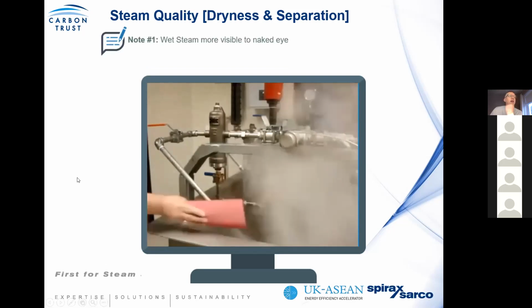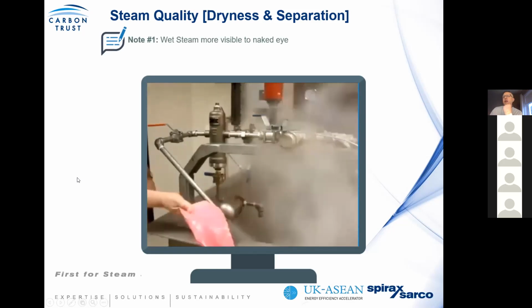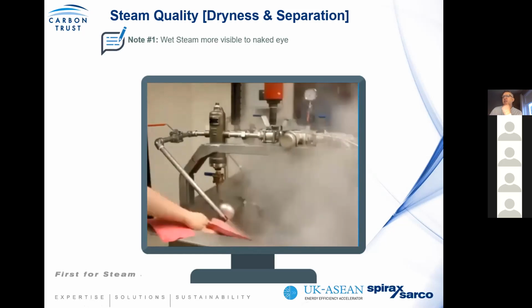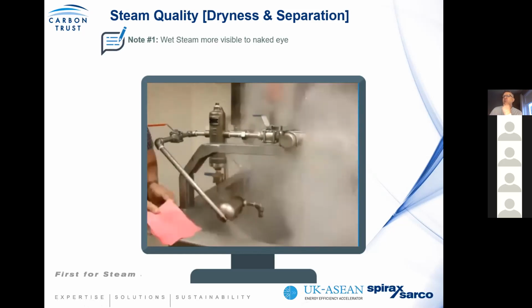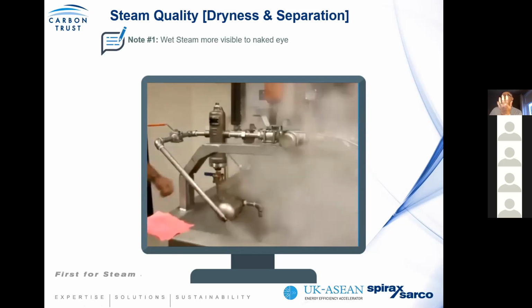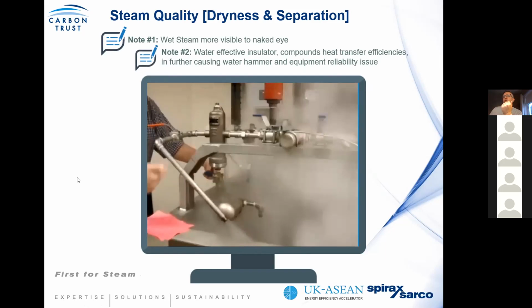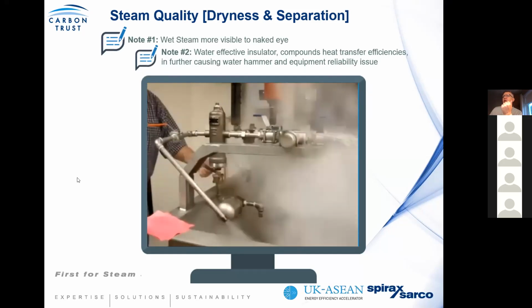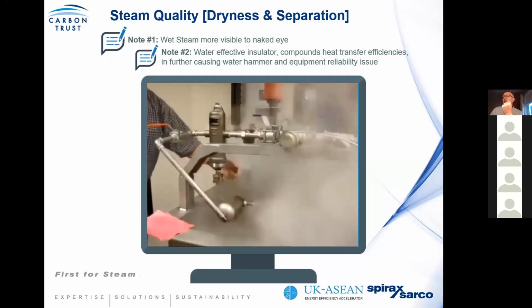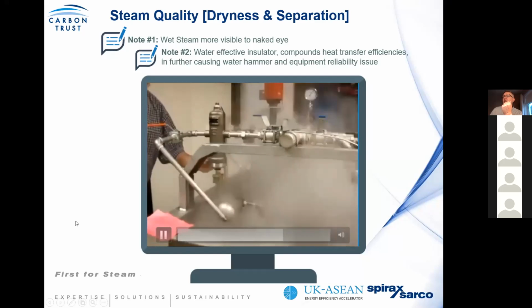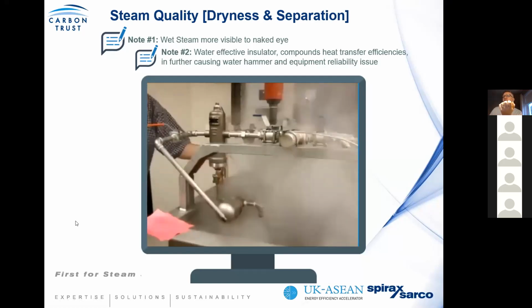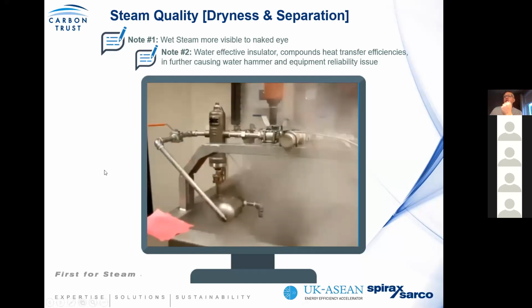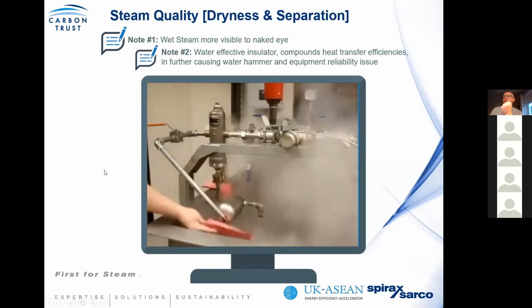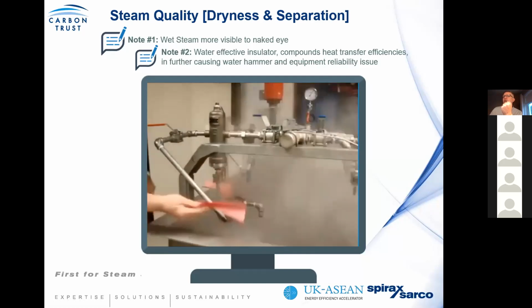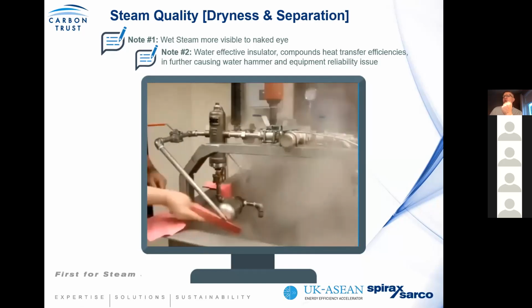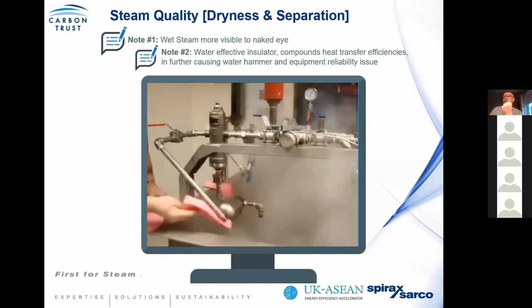It should be understood that wet steam is very visible to the naked eye. And you can see here, as he puts test pieces of paper in, how saturated the paper has become, because effectively the distribution steam contains a lot of water. Now, what he's looking to do here is bring the separator online. And as you can see here, the separator is removing those water droplets from the steam system, such that you get high quality steam to your user. He's now going to test his steam to his end user. And you can see that in this condition, the test paper is quite dry. So in other words, we are supplying high quality steam to the end user.